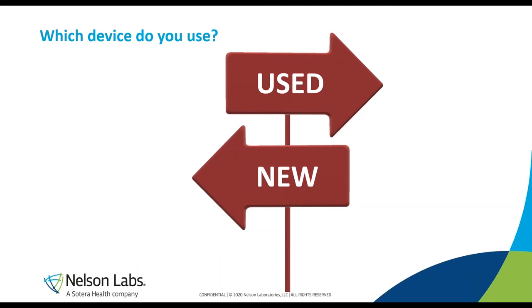A common question: what type of devices do you use for your validation — already used devices or new devices? The answer is: both are fine. Unlike cleaning validation, where you need used devices, for disinfection validation you can perform testing on new devices or used devices, including a simulated use situation. That makes it a little bit easier.